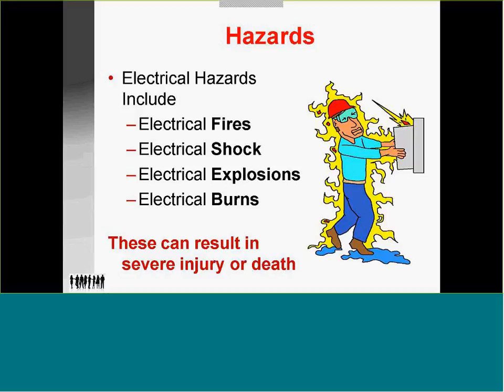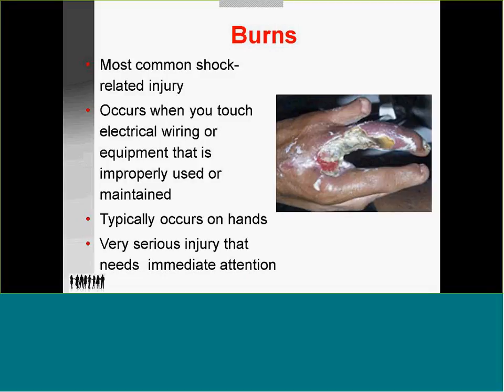These things cause us problems, and we're starting to see new numbers out because falling off a ladder, you would just call that a fall. Now it's associated with electricity. It's now being listed by the Bureau of Labor Statistics, so we're beginning to see a better picture of what electricity is doing. The most common is burns, and primarily in the hands where it takes place. Typically, it can penetrate very quickly. Natural skin can hold back 30 volts. Above that, it will penetrate.